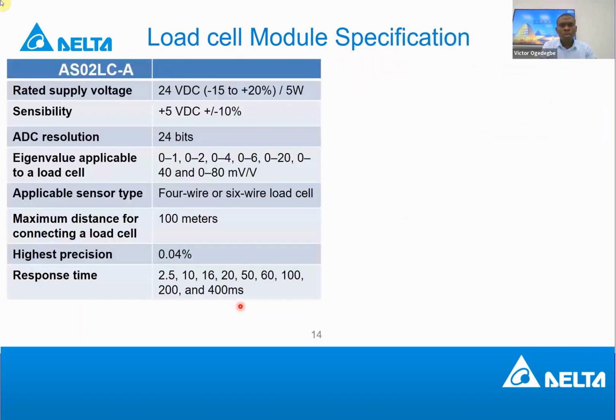So let's proceed and look at the specification of the load cell module. There are quite some specifications in the load cell module that are very important. For this load cell module, the model name is AS02LC-A. Then the power supply is 24 volts, like I showed you what I already have there. And the analog to digital converter resolution is 24 bits, so it's a very sharp conversion. And for the excitation voltage, the load cell module supplies the sensor the excitation voltage for the sensor to amplify the small voltage it has to a voltage that can be read to have the correct reading of the weight that's being measured.